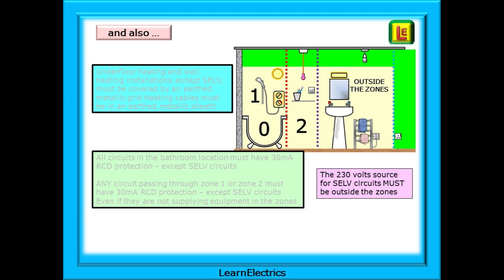A last point on SELV equipment: most SELV equipment will be supplied by a 230 volt transformer — what we call the source. That source, the 230 volt transformer and the 230 volt cables, must be physically situated outside the zones. Again, we are protecting the users from electric shock.